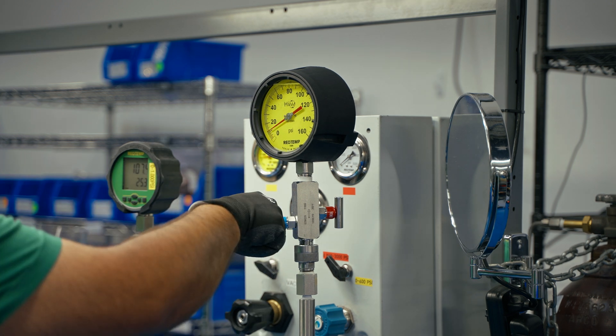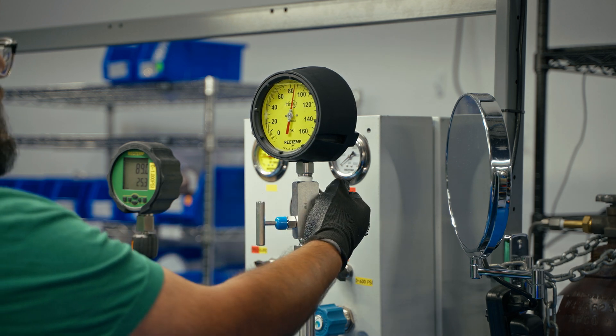Bring the line slowly up to operating pressure and watch for leaks or pointer jump. Confirm the pointer returns to zero when vented.